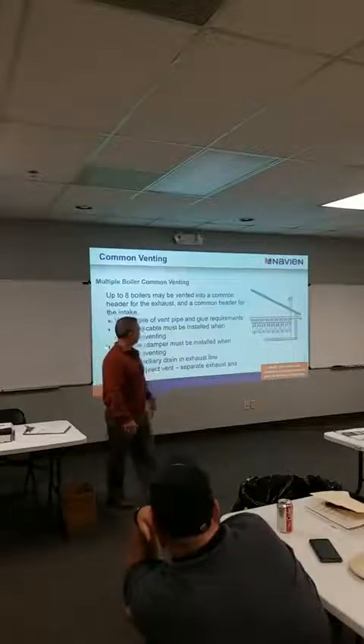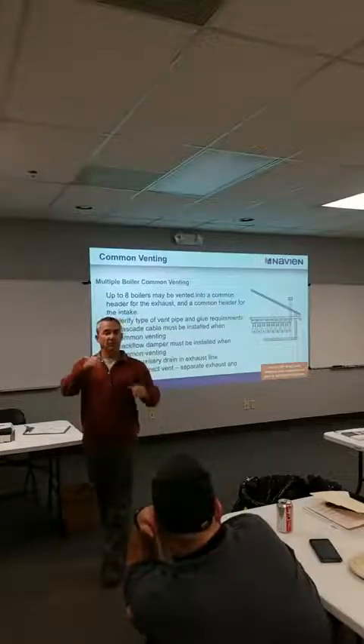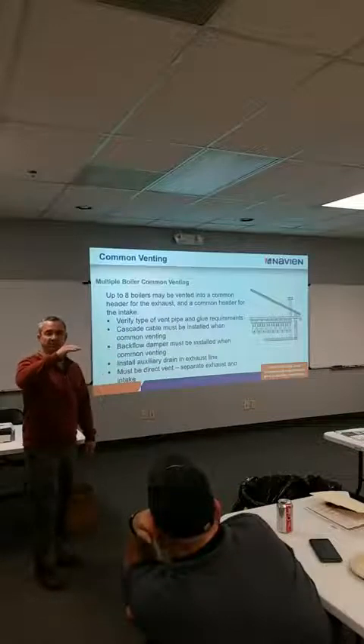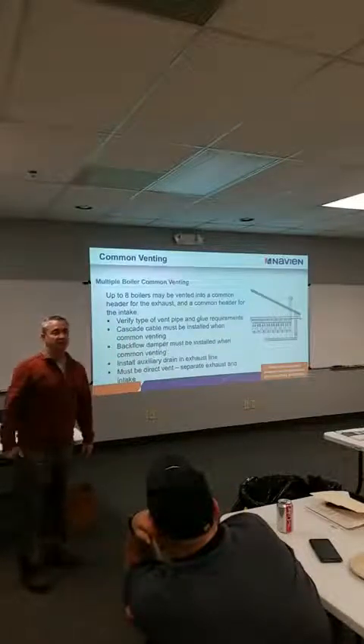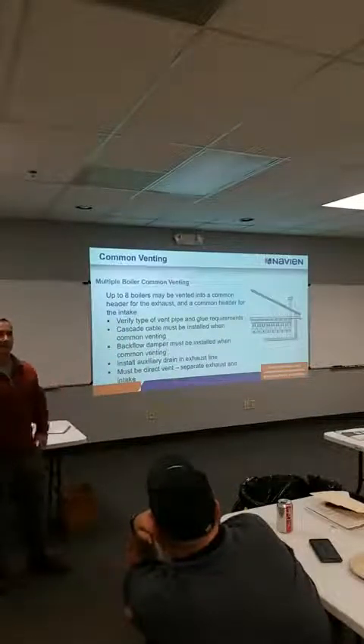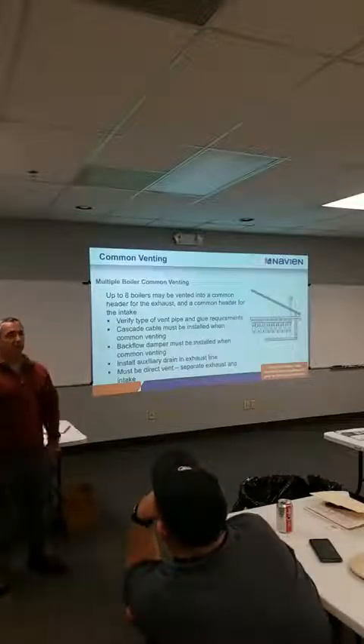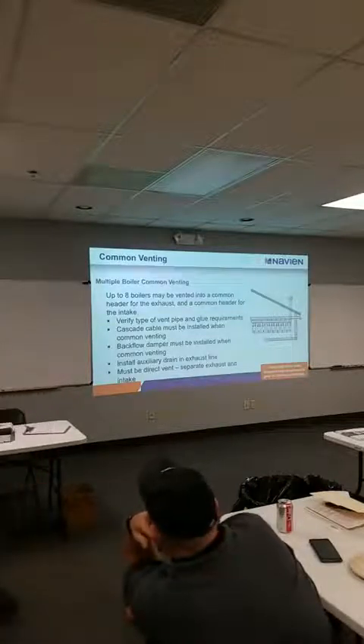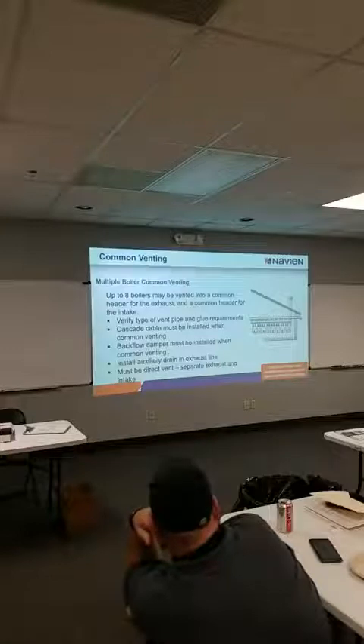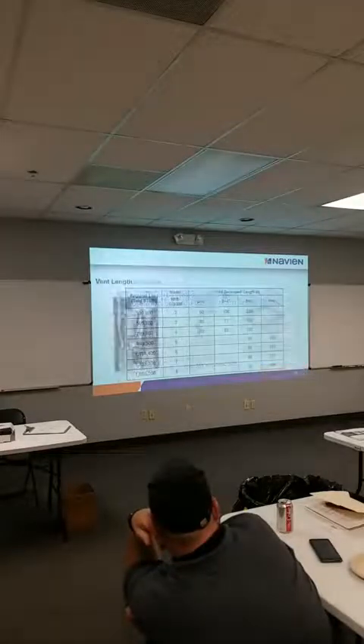I might have a better picture of it. Sort of like a drop header. Yeah, so that way you have a channel for condensate to build up and run to a condensate T. Oh, you come up and into it. Come up and elbow into your manifold pipe. So it's off the side instead of the bottom. Yeah, exactly. We learned that the hard way.